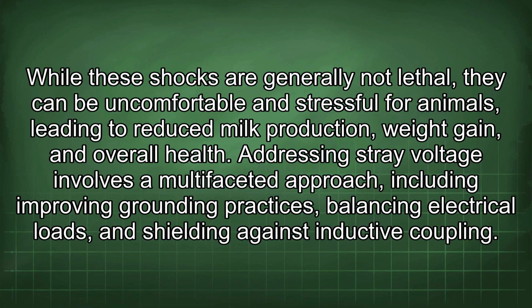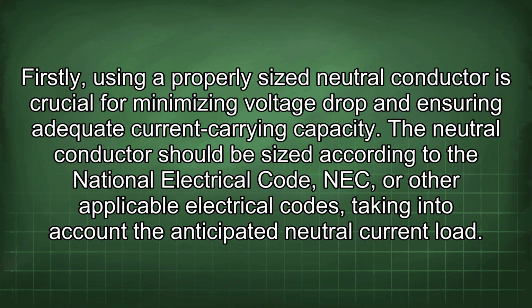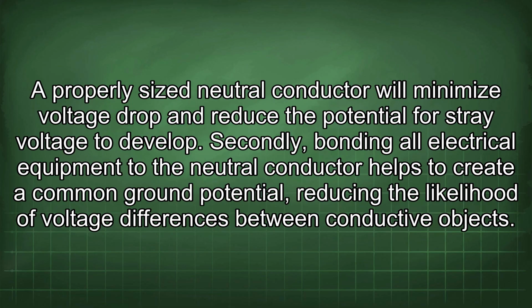Addressing stray voltage involves a multifaceted approach, including improving grounding practices, balancing electrical loads, and shielding against inductive coupling. Firstly, using a properly sized neutral conductor is crucial for minimizing voltage drop and ensuring adequate current carrying capacity. The neutral conductor should be sized according to the National Electrical Code, NEC, or other applicable electrical codes, taking into account the anticipated neutral current load. A properly sized neutral conductor will minimize voltage drop and reduce the potential for stray voltage to develop.